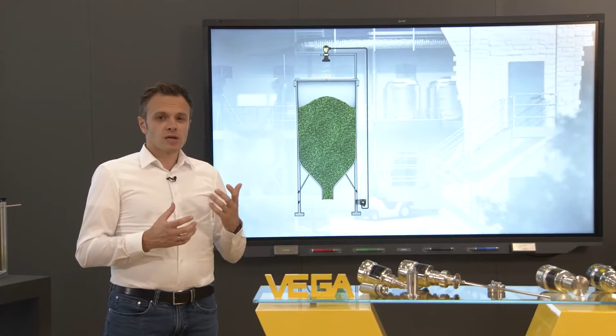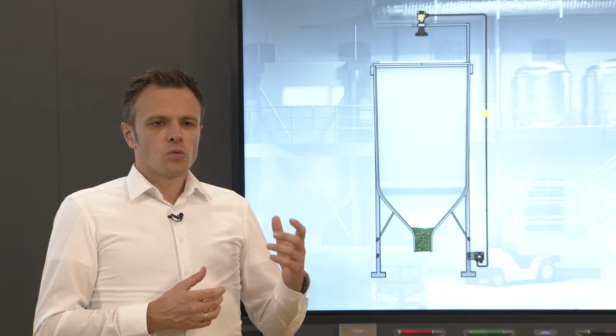Yeah, Natalie, for solid applications we also have a solution with our VEGA Pulse family. For example, for granulated goods, such as salt in the production of pharmaceutical goods, we have the storage in big packs. The big packs can also be measured with the VEGA Pulse 69, and the good thing is the VEGA Pulse 69 can measure through the closed big pack, so you don't have to open it. It's a similar situation to the Pulse 64 with the glass tank. So the VEGA Pulse 69 has good focusing at 80 GHz, so even the metal construction where the big pack is hanging in has no influence. You just measure the level internally, and it's very easy to follow the measurement.